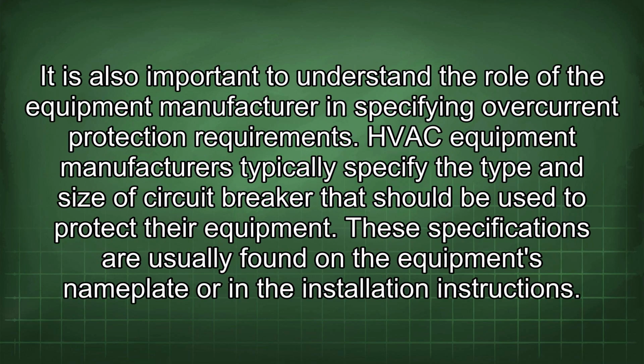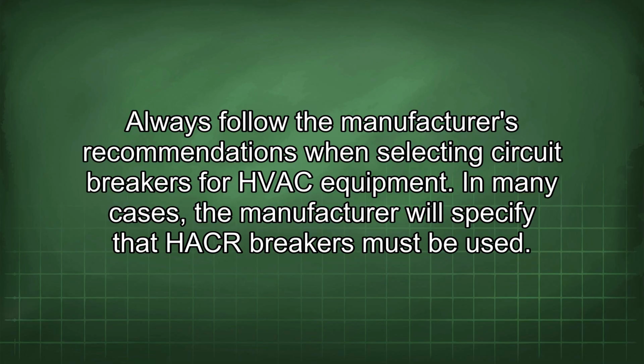equipment. It is also important to understand the role of the equipment manufacturer in specifying overcurrent protection requirements. HVAC equipment manufacturers typically specify the type and size of circuit breaker that should be used to protect their equipment. These specifications are usually found on the equipment's nameplate or in the installation instructions. Always follow the manufacturer's recommendations when selecting circuit breakers for HVAC equipment. In many cases, the manufacturer will specify that HACR breakers must be used.